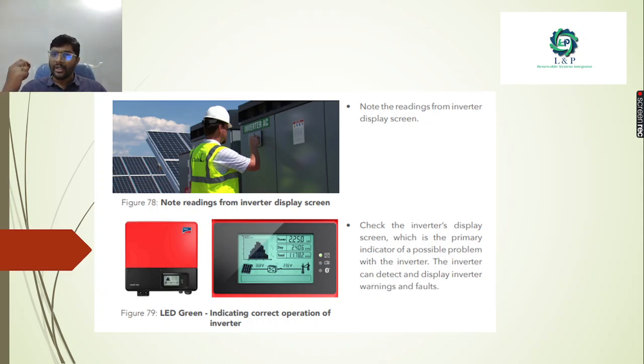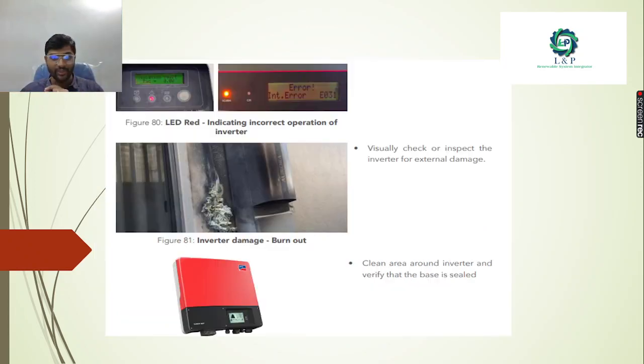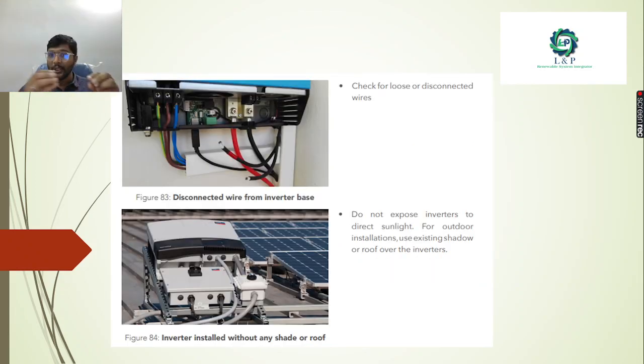Next, whenever you're going to do a maintenance operation, note down the readings from the inverter display screen. What is the power, what is the voltage, what is the current that you can see. Is the inverter showing any fault indications? Has the inverter detected any warnings or faults? That's the first thing you need to do. Then visually check and inspect whether any external damage has occurred. Sometimes there is a possibility for errors to happen, or burning out. Make sure the inverter area is very clean and its base is sealed properly, and check whether there are any loose or disconnected wires.